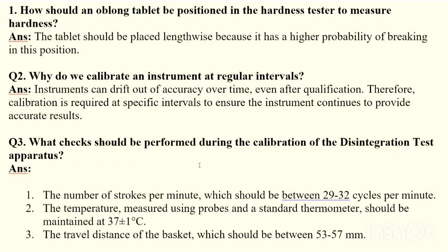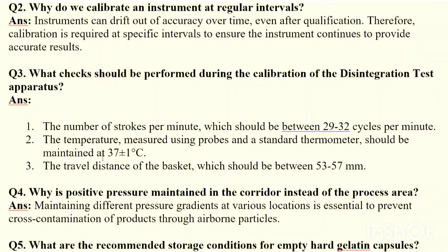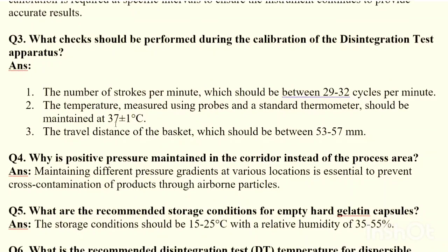What checks should be performed during calibration of a disintegration test apparatus? For the disintegration apparatus, the temperature of the bath is measured — whether the probes are maintaining 37 ± 1°C, which can be verified using a thermometer. The travel distance of the basket should be between 53 to 57 mm, and the number of strokes per minute as well as stroke length need to be tested.